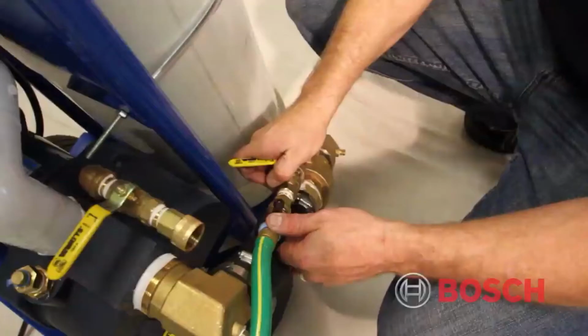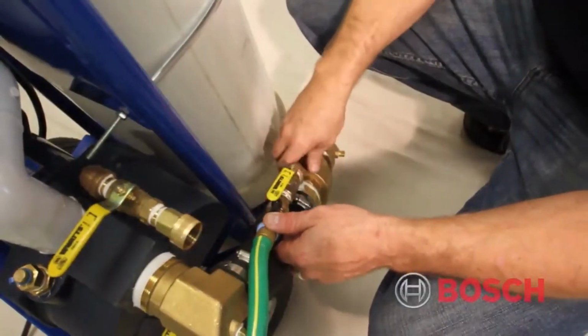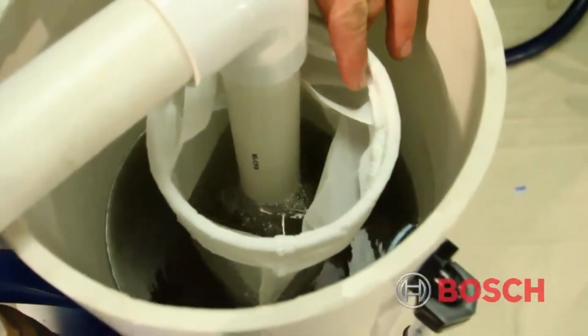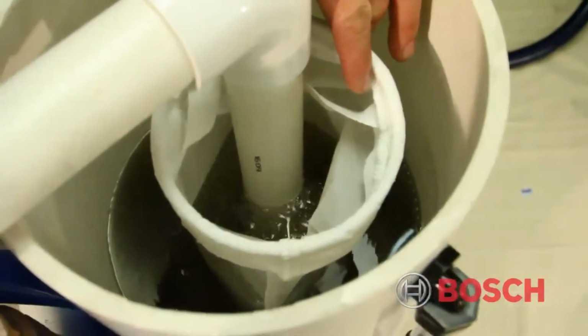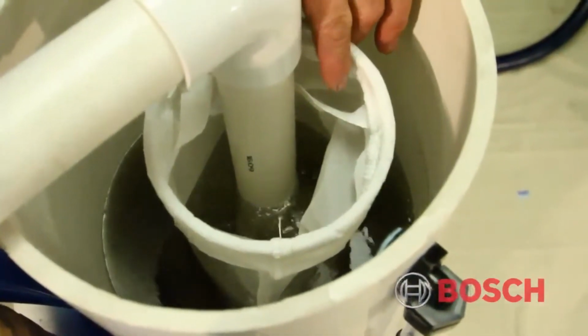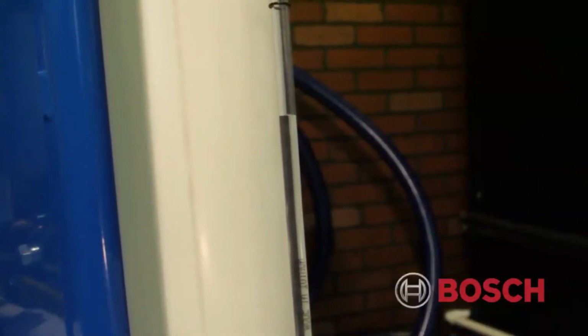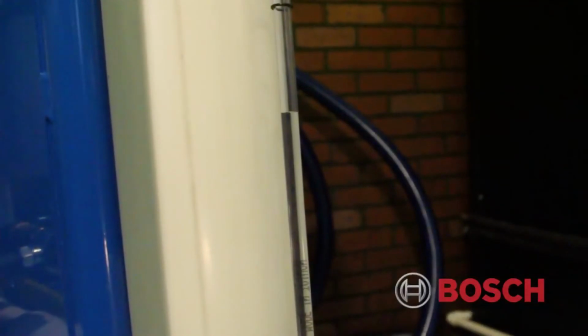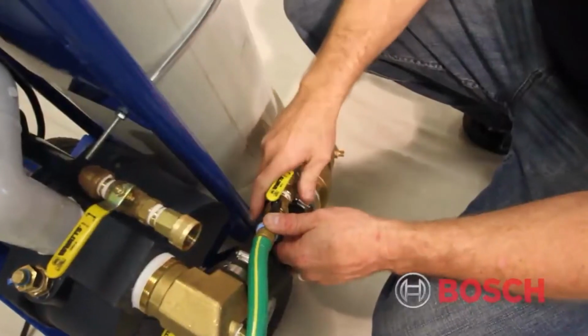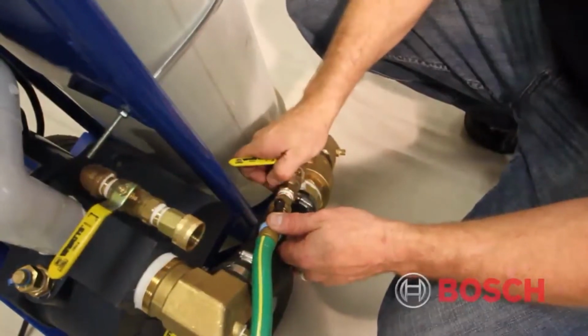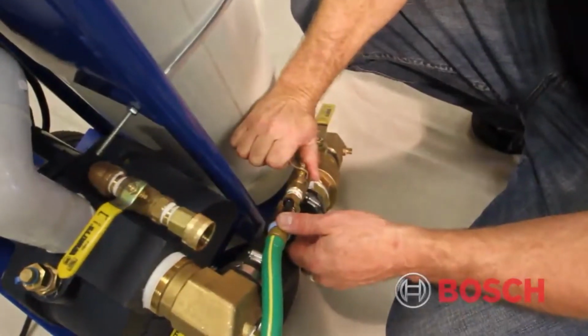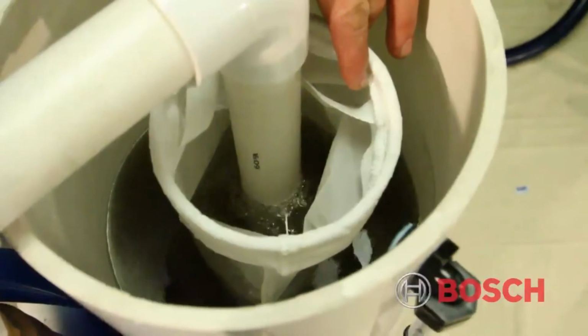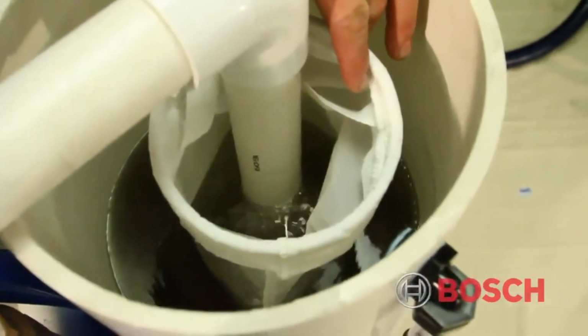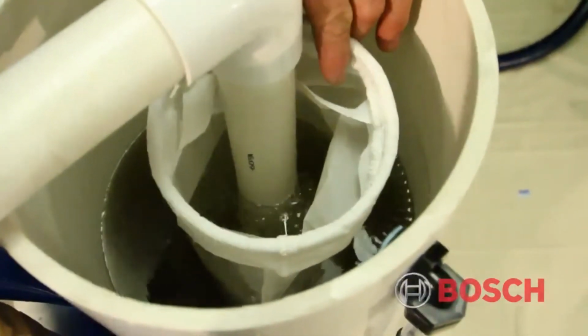As the water drops, add more by opening the 1/2-inch garden hose fill valve. Note, watch the fluid, making sure the water level never drops below the flush cart suction port or runs over the top of the reservoir. Once the reservoir water level is reasonably stable or begins to increase, turn the makeup water down or off as conditions dictate. Observe the discharge water as it re-enters the reservoir. Watch for air bubbles being discharged into the reservoir.